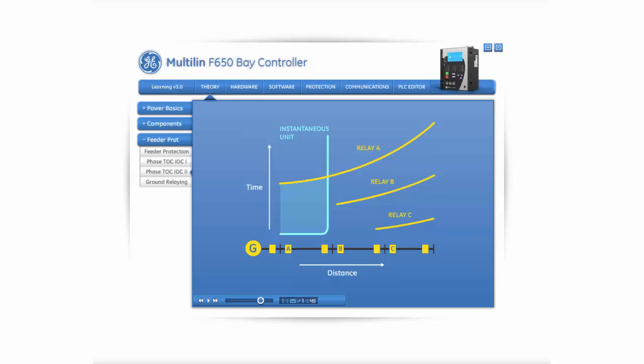Under certain fault conditions, this could be a disadvantage, and so instantaneous overcurrent elements are used in conjunction with the time overcurrent elements to provide high-speed primary protection. These elements must be set to pick up under maximum fault current conditions for three-phase faults somewhat short of the end of the line. The shaded area of the figure illustrates the improvement in tripping time obtained with instantaneous elements.